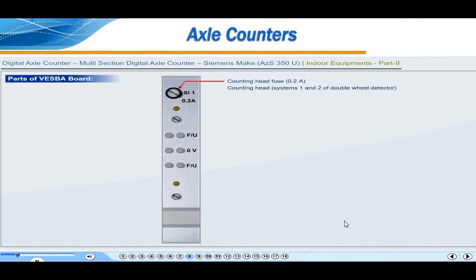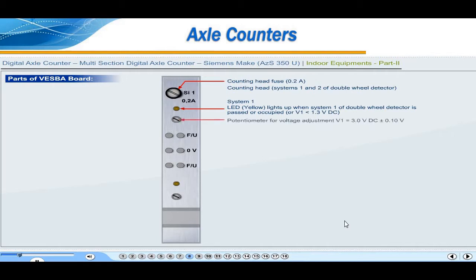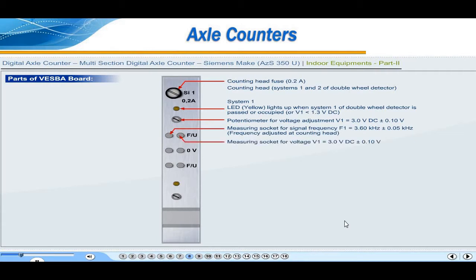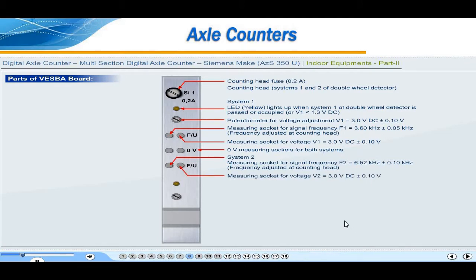0.2 amperes counting head fuse, which is used for both system 1 and 2 of double wheel detector. Yellow LED, which lights up when system 1 of double wheel detector is passed by an axle or V1 is less than 1.3 volt DC. Potentiometer used for adjustment of V1. Measuring socket for frequency F1. Measuring socket for voltage V1. 0 volt measuring socket for both systems. Measuring socket for frequency F2. Measuring socket for voltage V2.